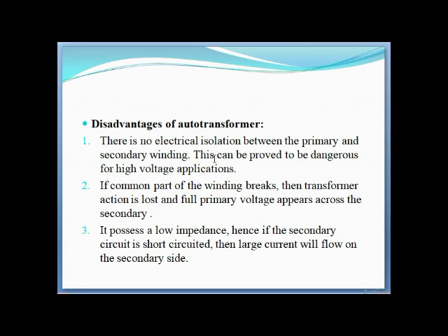Another disadvantage: if the common part of the winding breaks, transformer action is lost and the full primary voltage appears on the secondary side. Also, the auto transformer possesses low impedance, so if the secondary circuit is short-circuited, a very large current will flow on the secondary side.